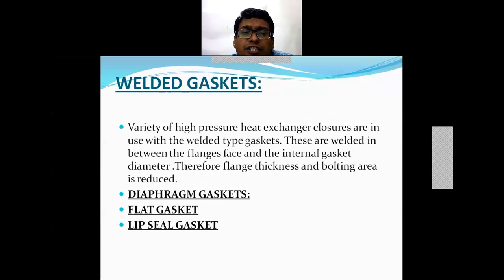The next is a welded gasket, that is the variety of high pressure heat exchangers. These welded gaskets are used in case of high pressure heat exchangers, and they are directly welded to the heads. In a floating head heat exchanger, the other end of the heat exchanger, which is at a higher temperature and higher pressure, there to prevent the leakages, you are using these welded gaskets. That means they are actually welded to the flange. So these are welded in between the flange faces and the internal gasket diameter. So therefore the flange thickness and the bolting area that reduces.